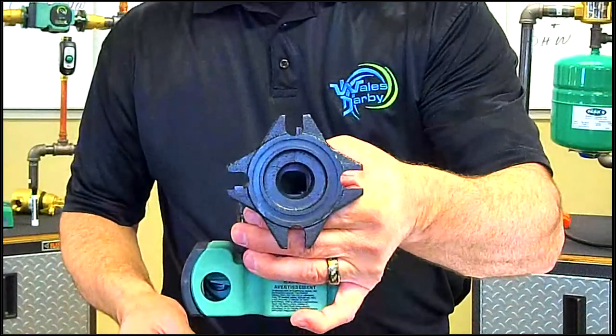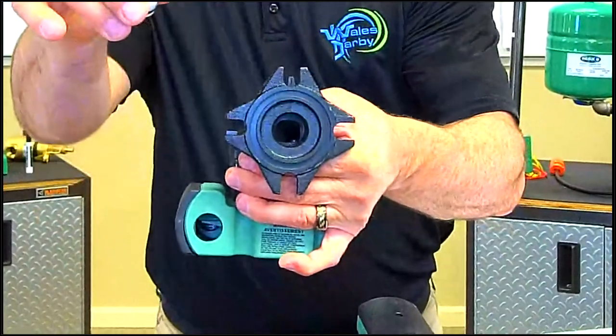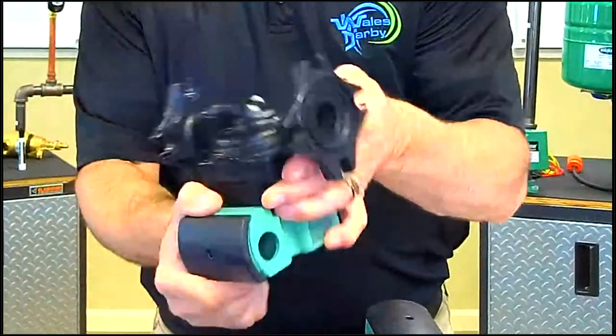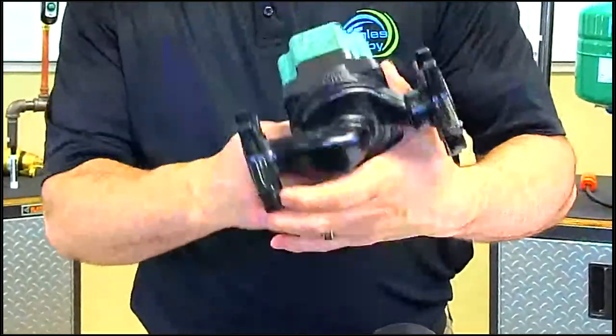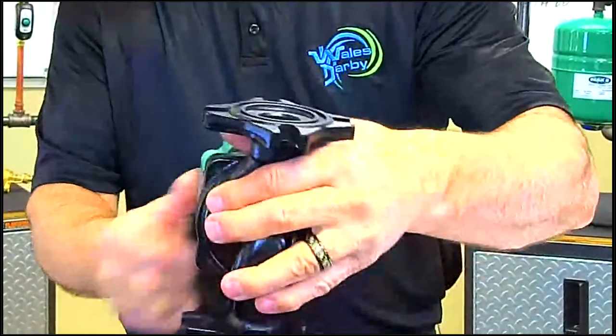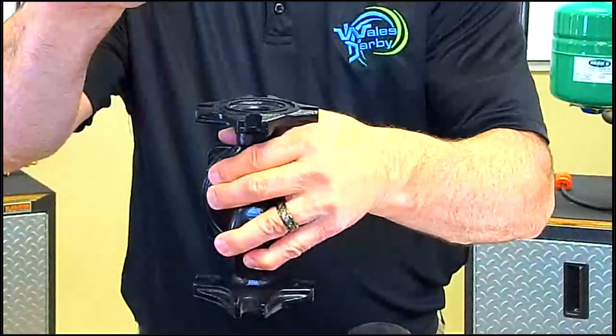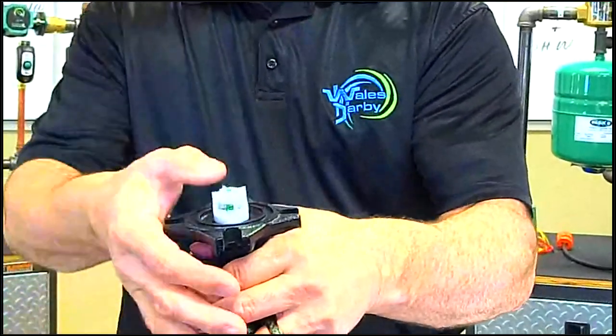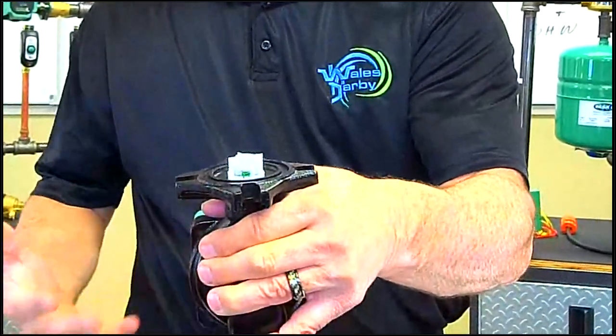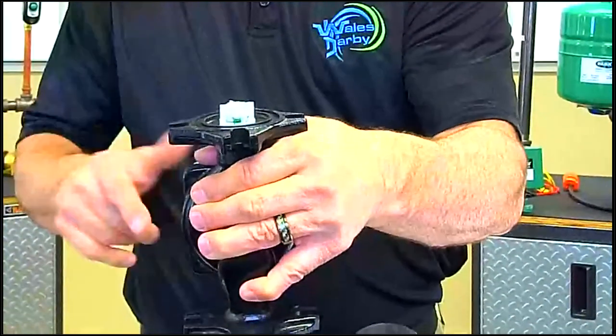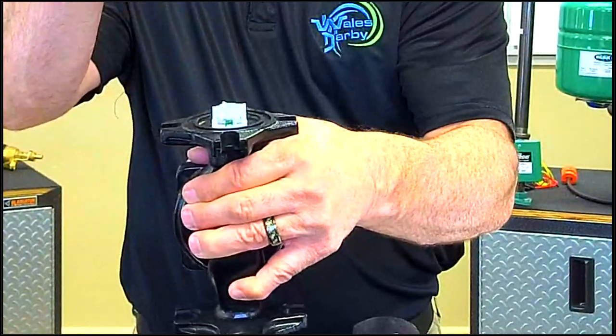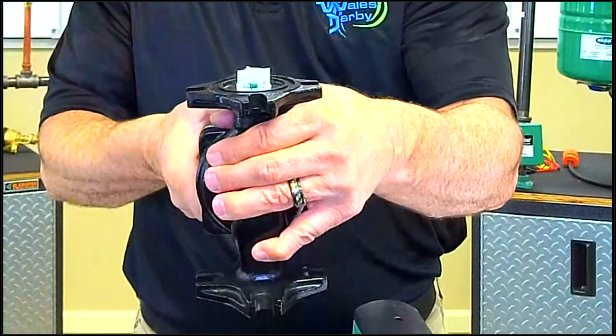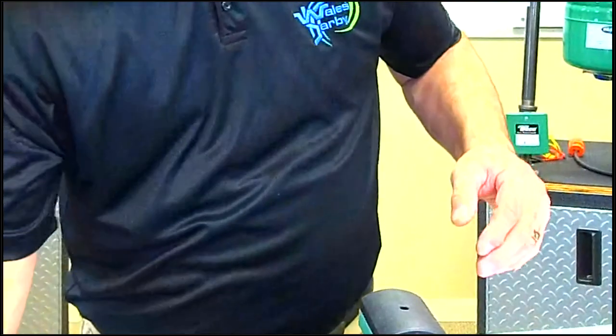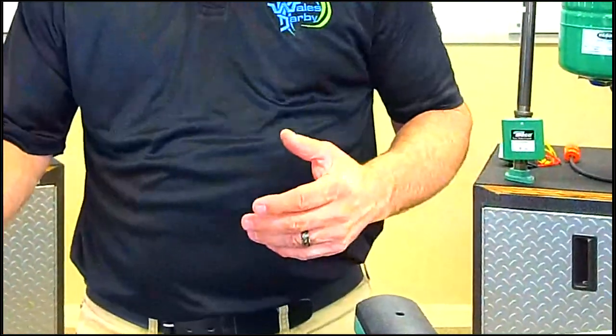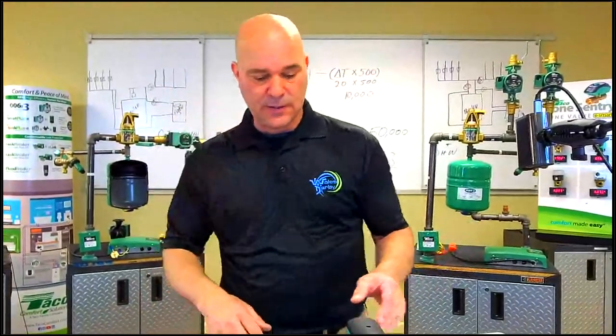Each circulator flange is set at the outlet side. So there's an arrow here on the circulator, and the arrow is facing up. I would take the O-ring, put the O-ring in first, and then push that in. That's an installed IFC. When the circulator comes on, it will lift the internal flow check and it will circulate water throughout the system. So that's how they install. That part is available. If you're doing a lot of OEM product and you want to put an integral flow check in there, that little flow check is available.